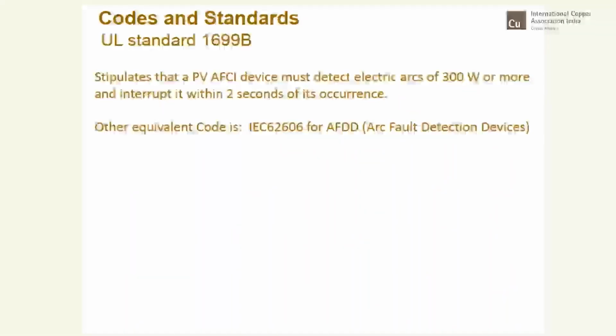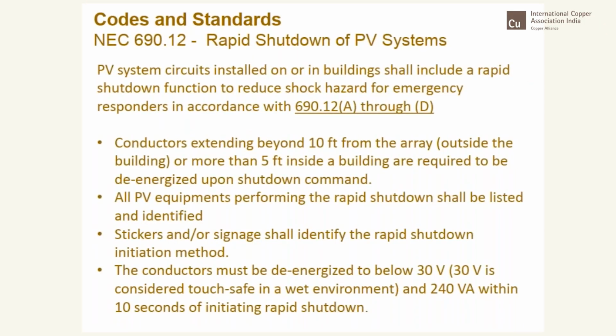It stipulates that the PV-AF-CI device must detect electrical arcs of modules as low as 300-watt, and it has to shut down in 2 seconds. So there are other equivalent codes, IEC codes, which were highlighted by Mr. Das. Now the next one is about 690.12, which is the rapid shutdown of PV systems, which was discussed a little earlier.